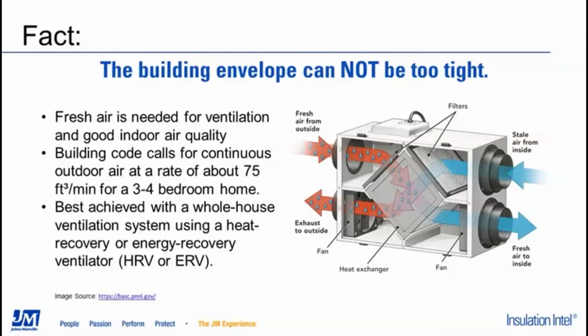Both residential and commercial building codes call for fresh outdoor air to be delivered to our buildings for good indoor air quality. The residential code calls for an airflow in cubic feet per minute equivalent to 3% of the floor area plus 7.5 CFM per occupant. So that works out to around 75 CFM total for most 3 to 4 bedroom homes. The best way to deliver fresh air is through a whole house ventilation system that includes an HRV or ERV, which is a heat recovery or energy recovery ventilator.